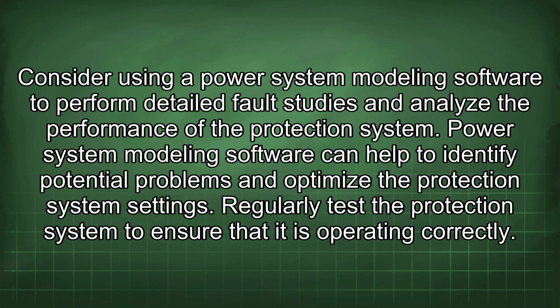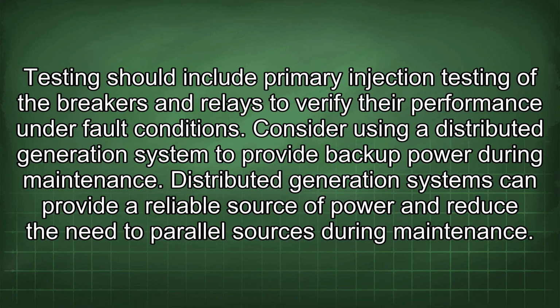Consider using power system modeling software to perform detailed fault studies and analyze the performance of the protection system. Power system modeling software can help to identify potential problems and optimize the protection system settings. Regularly test the protection system to ensure that it is operating correctly. Testing should include primary injection testing of the breakers and relays to verify their performance under fault conditions. Consider using a distributed generation system to provide backup power during maintenance.